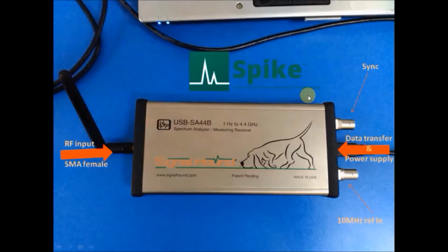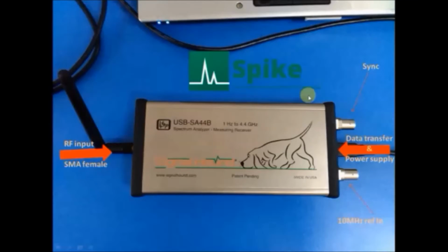And on the rear panel we can see two BNC connectors, one for synchronization with the tracking generator, which works as a scalar network analyzer. The other one is a standard 10 MHz external reference. Now at the input we have one cellular antenna for demonstration.